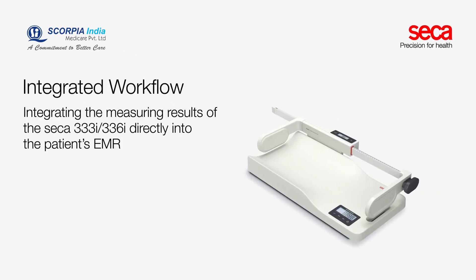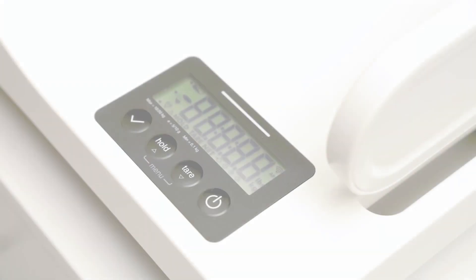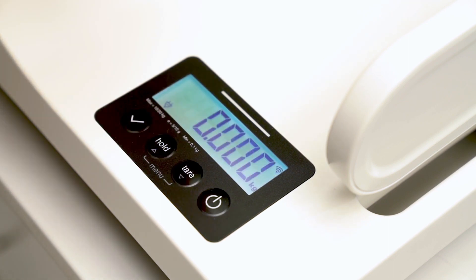This seca baby scale can transfer the baby's weight directly into its personal medical record of your facility's EMR system. With the optional digital measuring rod, the baby's length can be transmitted at the same time. The system is operational when the scale is turned on and the Wi-Fi symbol stops blinking.